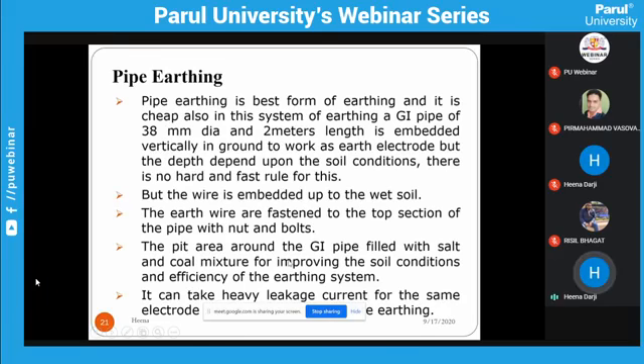Now pipe earthing. Pipe earthing is the best form of earthing, and it is cheap also. In this system of earthing, a GI pipe of 30 mm dia and 2 meter length is embedded vertically in the ground to work as the earth electrode, but the depth depends upon the soil conditions, and there are no hard and fast rules for this.